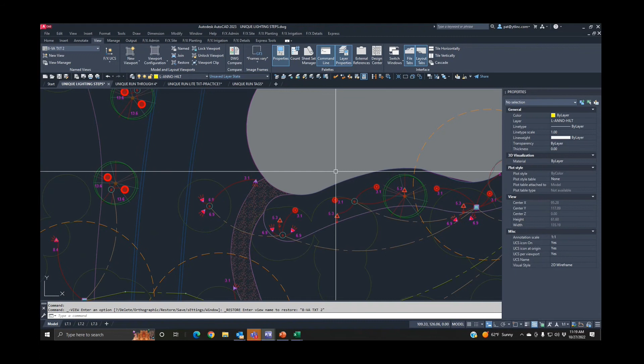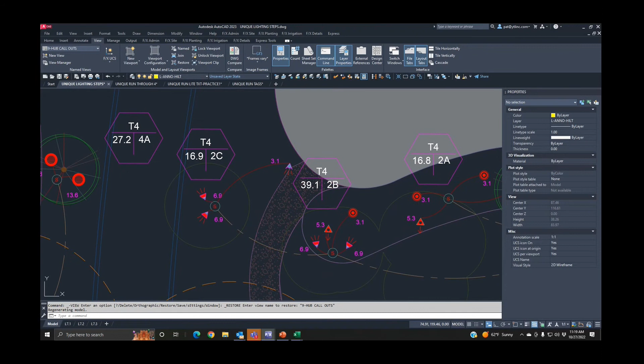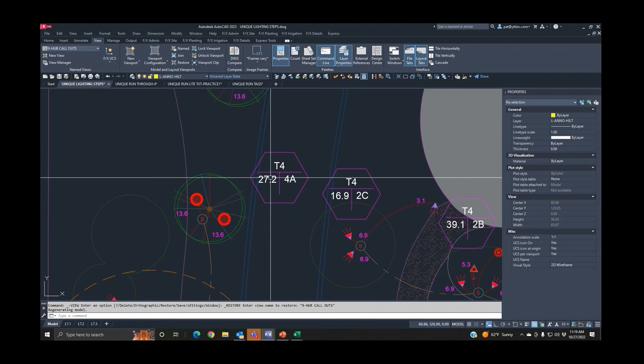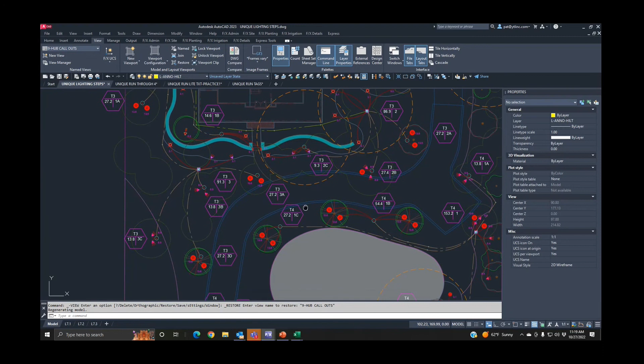Once we have all of those in the design, we then do a hub callout. We show this on all of our designs - it's just a little custom block we built, no big deal, real easy to do. This callout is calling out this S-Hub, telling us that transformer 4 on this S-Hub has a VA of 27.2, and this hub is wired to wire number 4A. We show that on every single hub throughout the design.